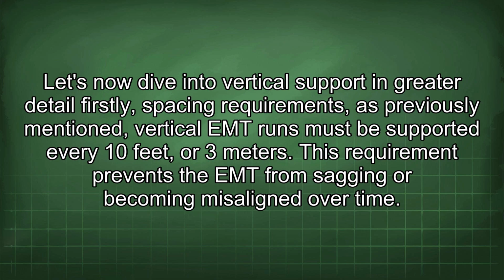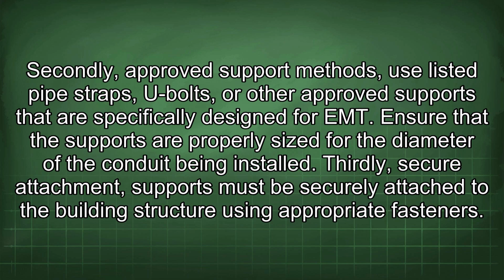Firstly, spacing requirements. As previously mentioned, vertical EMT runs must be supported every 10 feet, or 3 meters. This requirement prevents the EMT from sagging or becoming misaligned over time. Secondly, approved support methods. Use listed pipe straps, U-bolts, or other approved supports that are specifically designed for EMT. Ensure that the supports are properly sized for the diameter of the conduit being installed.